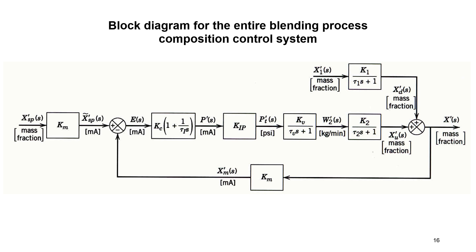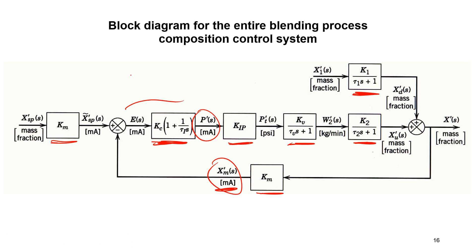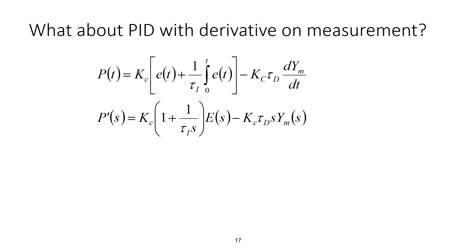We have now put in all the different transfer functions: the measurement, the PI controller, KIP, the valve, the process, and the disturbance. I've also labeled these with standard units typical in process control — pneumatic signals and milliamp signals going into a PID block. In modern DCS (distributed control systems) everything is digitized and occurs within the computer, but once it reaches the valve that's a PSIG signal to a pneumatically actuated valve affecting flow rate. For the purposes of this class, we'll assume milliamp signals.